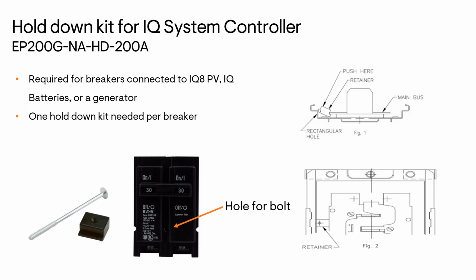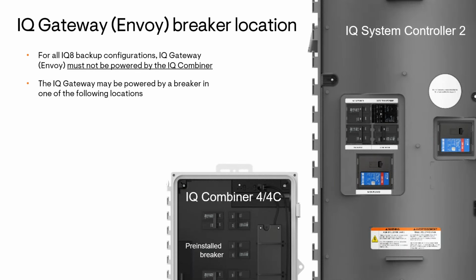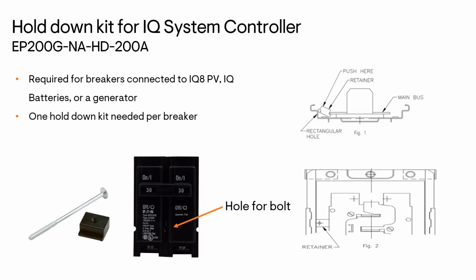The hold-down kit for the IQ system controller is not the same as the kit for the IQ Combiner 4C. This is an important thing to note. With this hold-down kit, it's a 1-for-1 kit as opposed to 2-for-1 like the combiner kit. So 1 kit is needed for each individual breaker. So before I move on to the next slide, I want to see if there are any questions because I know sometimes the hold-down kit topic can be a little confusing because we have the 2 different components with different kits.